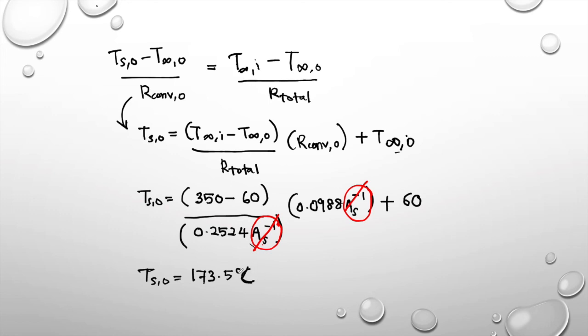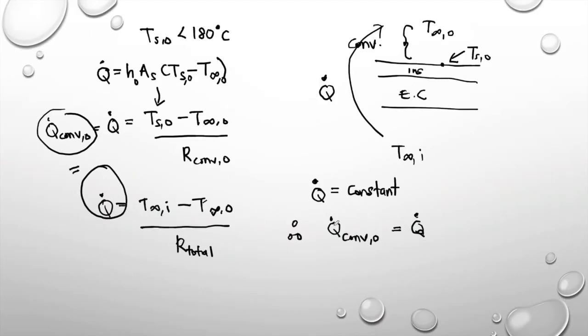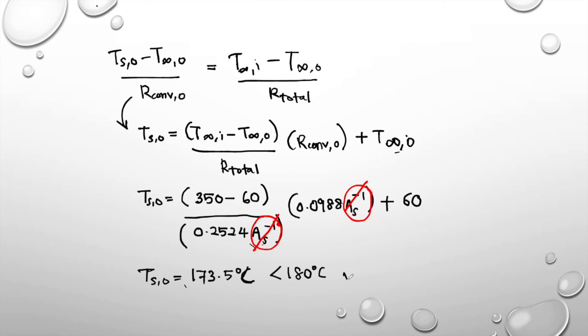The temperature T_s,out of 173.5 degrees Celsius is below 180 degrees Celsius. Therefore, what was suggested by the plant supervisor — increasing the cooling air velocity by 10 percent — is proven effective to prevent fire hazard. That's all for Example 3. Thank you.